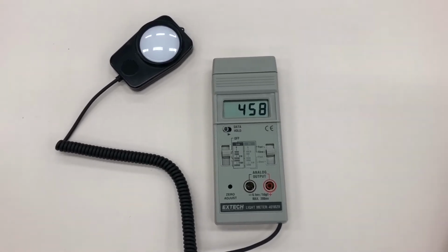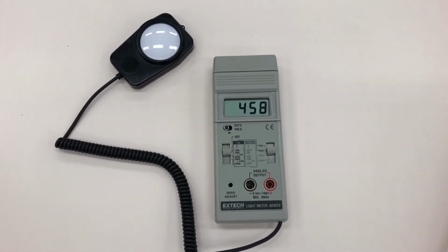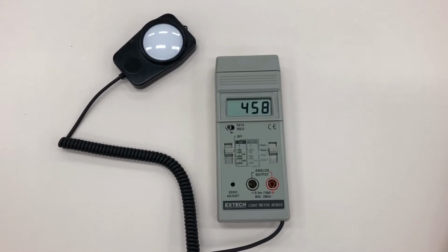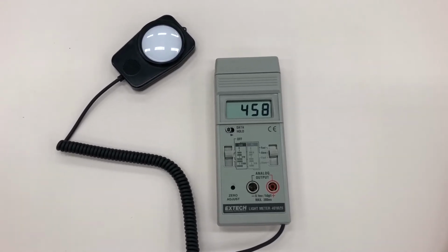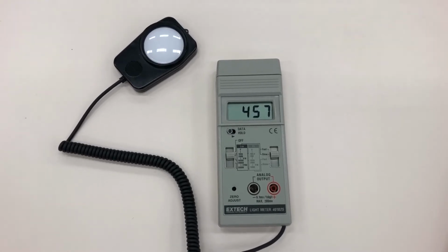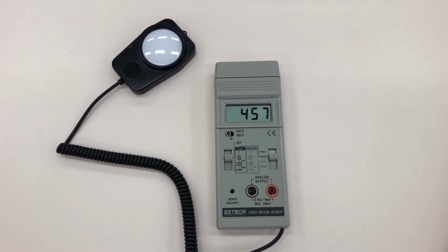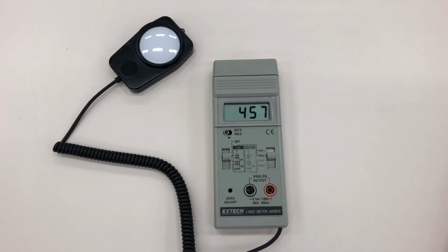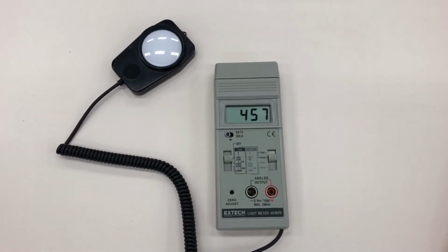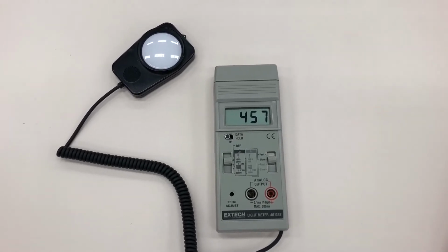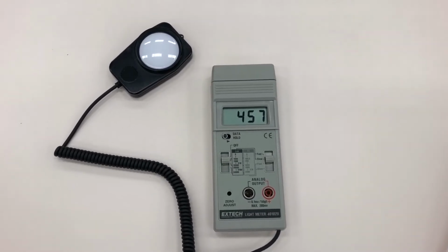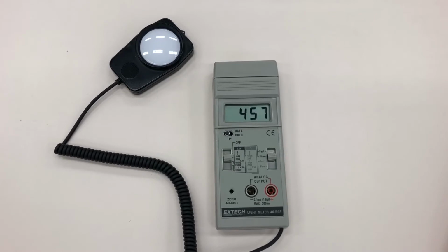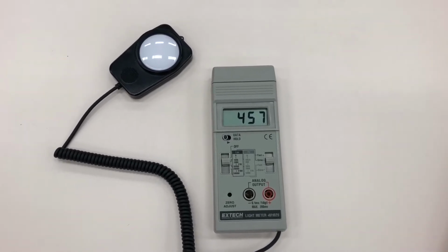First off, in terms of lighting, we have a foot candle or a lux meter. And so just a couple definitions to get you started. If we're looking at luminous or light flux, that's the energy that's given off by a source. And so the units for that are going to be in lumens. Secondly, illuminance is the amount of light that actually falls onto a surface. So the unit for that is a lux, and 1 lux is approximately equal to 1 lumen per square meter. 1 foot candle is about 10.7 lux.